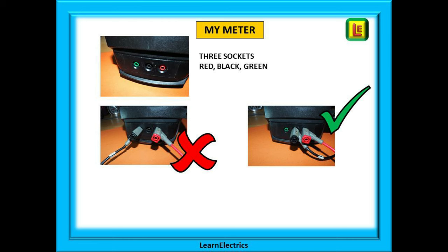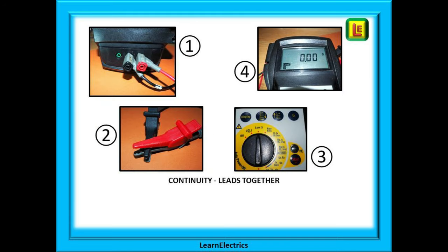My meter has three sockets for the test leads at the top edge, colored red, black, and green. Continuity testing is a dead test so I only need two leads — the red and the black. It does matter that I put them in the correct holes since using the wrong hole will give me the wrong results. My meter uses the red and black sockets; another meter I had used the red and green sockets. Know your meter. The first steps to proving correct meter function are: number one, put the test leads into the correct sockets; number two, link the leads together with the crocodile clips; number three, set your meter to the low ohms continuity range; and number four, press the test button and observe the results.